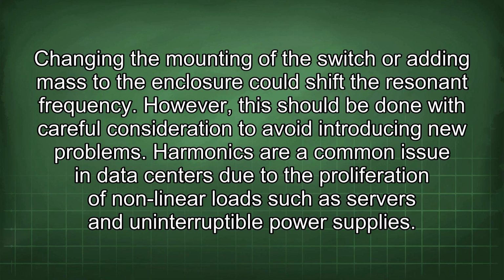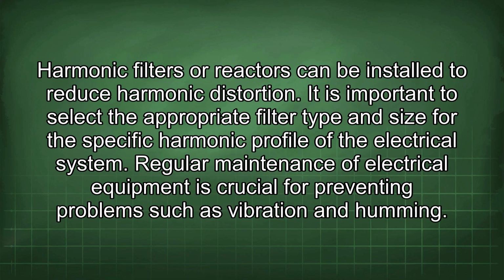Harmonics are a common issue in data centers due to the proliferation of nonlinear loads such as servers and uninterruptible power supplies. Harmonic filters or reactors can be installed to reduce harmonic distortion. It is important to select the appropriate filter type and size for the specific harmonic profile of the electrical system.